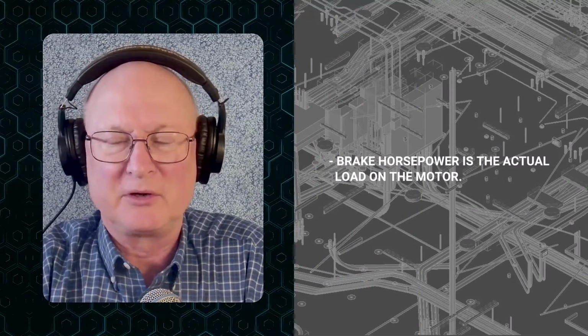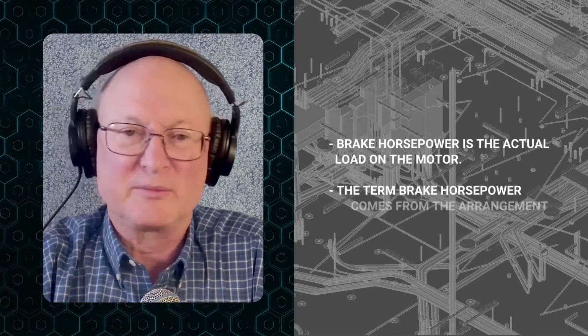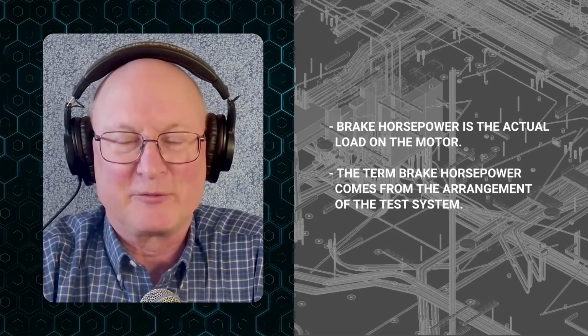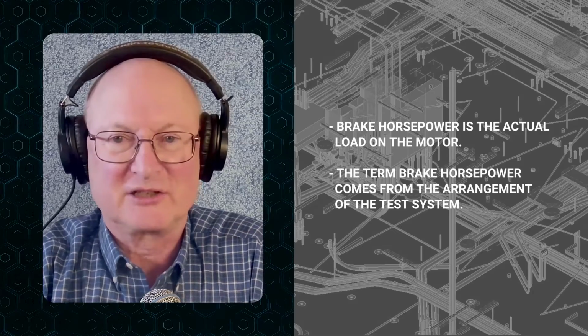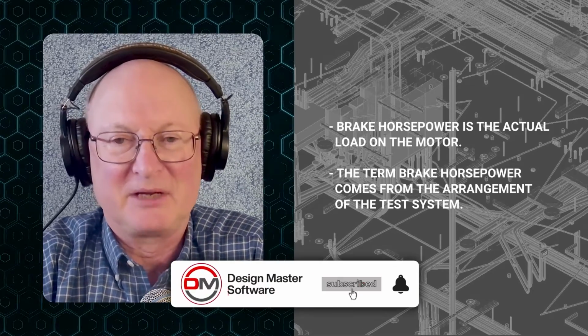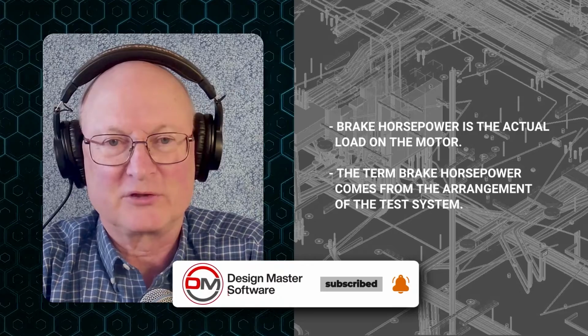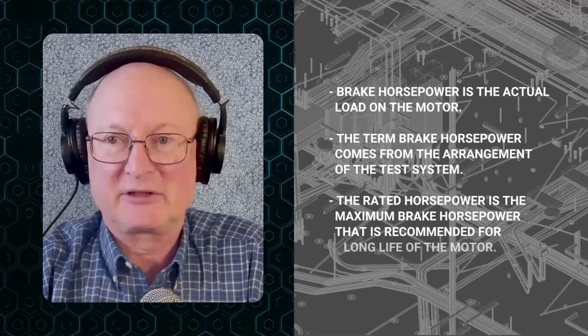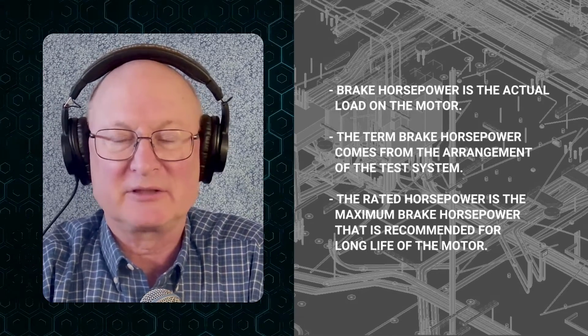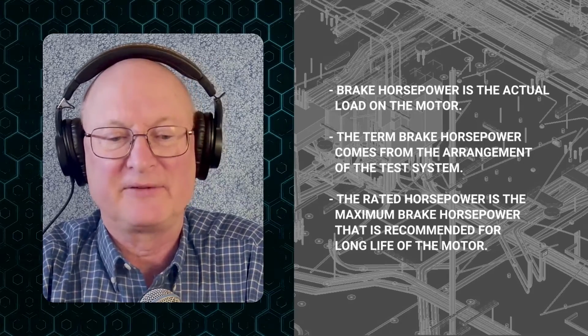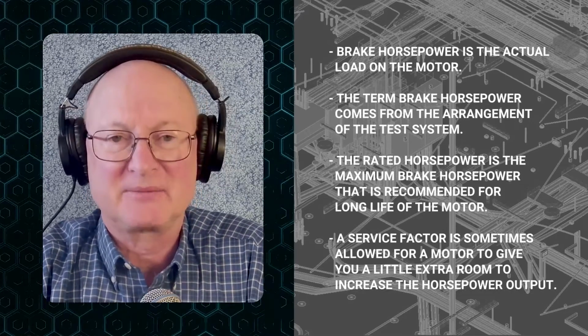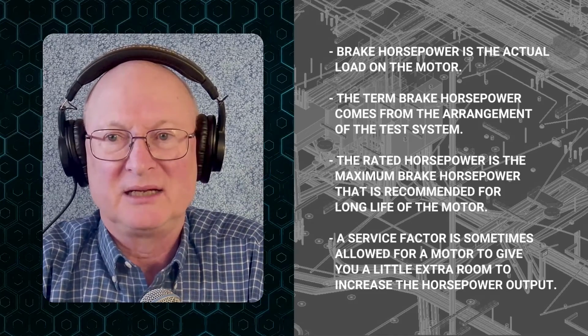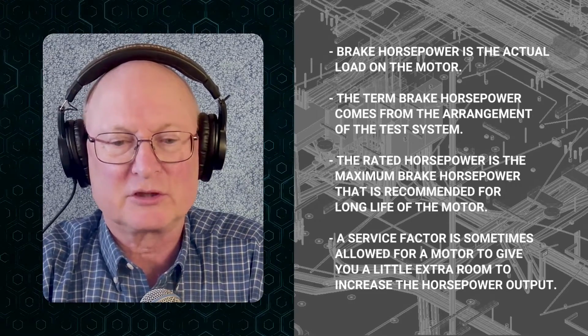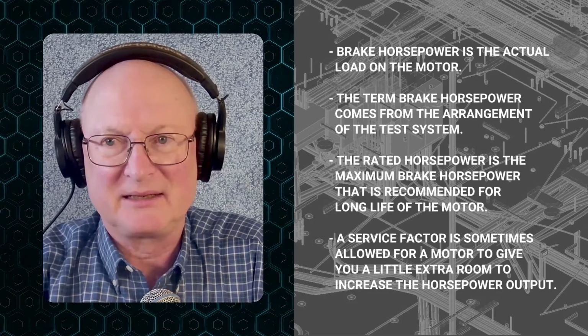All right, so let's review what we've talked about with brake horsepower today. Okay, brake horsepower is the actual load on the motor, not the rated horsepower. And the term brake horsepower, again, simply comes from the arrangement of the test system where they put a brake on the motor and measure the horsepower as the force of the brake increases. The rated horsepower is simply the maximum brake horsepower that is recommended for long life of the motor. A service factor is sometimes allowed for a motor to give you a little extra room to increase the horsepower output, but it's not recommended as a design point.